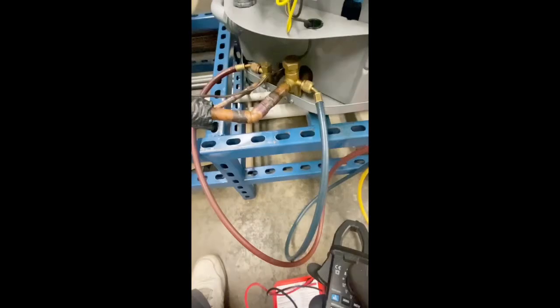And the fan is supposed to be running at 0.63 amps. So what I'm doing now is I'm checking the amperage on that fan. Because there's not much of a load for it to dissipate, the fan doesn't have to work that hard. So you're just going to put like 0.4 or 5 on there. It's kind of confusing at first, but once I realized there's no real load just because it's already in a climate controlled room.